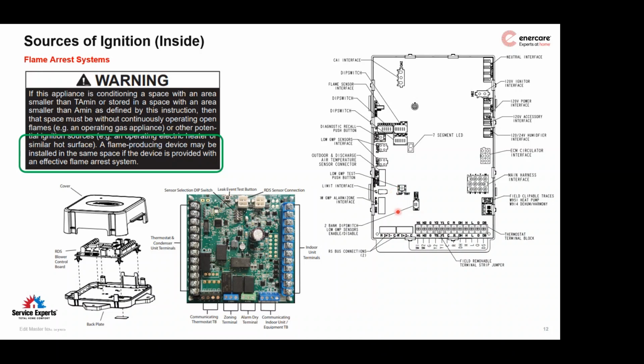And then the dip switches down here to set it up. These are the furnaces like the EL296, like we talked about, or 297V, and their EL290, or sorry, SLP99 UHV is also going to be equipped with these boards. So if you are installing a new system, it should already come equipped with this board. You shouldn't have to worry about installing an external one, and then everything wires up just as it normally did. This external one is the only real bolt on if you're putting in something with a legacy system. And we'll get into these a little more in depth as we go along, but that's basically what you're going to find.